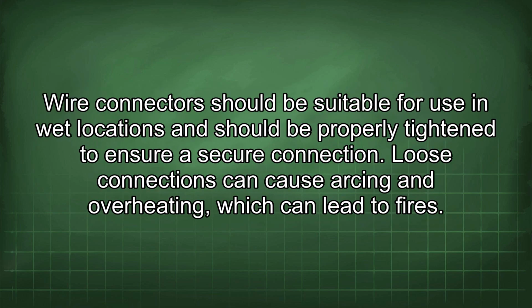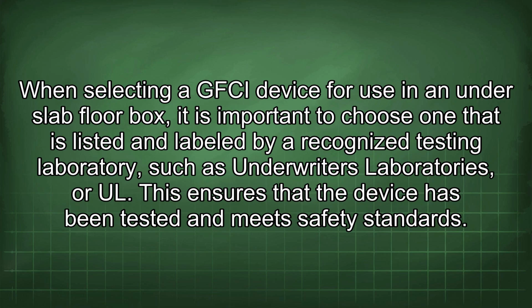Furthermore, all electrical connections within the floor box should be made using approved methods and materials. Wire connectors should be suitable for use in wet locations and should be properly tightened to ensure a secure connection. Loose connections can cause arcing and overheating, which can lead to fires. When selecting a GFCI device for use in an under-slab floor box, it is important to choose one that is listed and labeled by a recognized testing laboratory, such as Underwriters Laboratories, UL. This ensures that the device has been tested and meets safety standards.